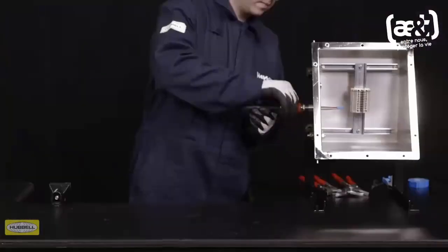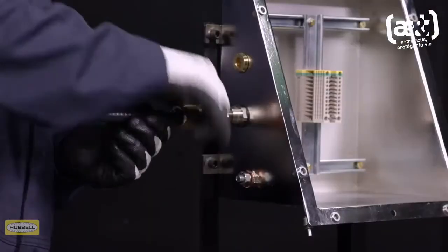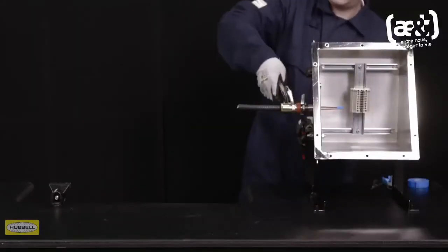Slide the cable through the entry until the pot is seated in the entry. Hand tighten the middle nut to the entry and add a fifth to a quarter turn with the wrench.